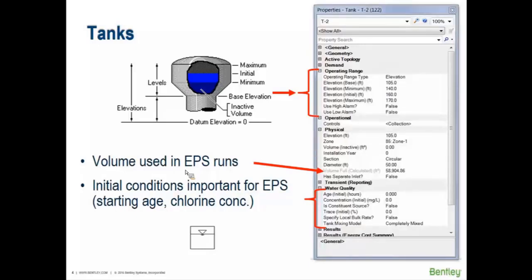When we get into water quality, you can enter the initial age in a tank and the initial concentration — perhaps chlorine concentration. Initial conditions in a water quality model really matter during a water age analysis because the water in a tank already has a particular age; it didn't start from zero. It might be two weeks old, one week old, or it has some chlorine level in it.